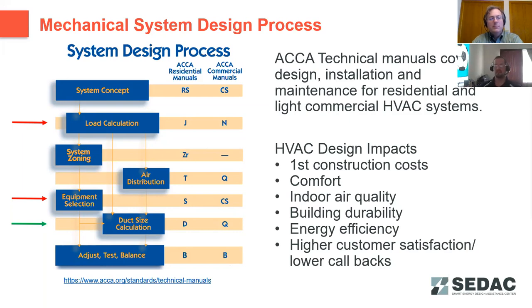for duct sizing. Although it's not a requirement of the code, it can be very beneficial because it helps ensure that the airflow through your duct system is going to be evenly distributed and meet the individual space loads within your structure. It's not uncommon for a lot of residential buildings to see balancing dampers put in the ductwork, and on callbacks from the customer, or during finalizing of the house when they're doing final touch-up painting and things like that, they'll adjust those dampers in order to balance the airflow. If they'd done a Manual D calculation, they wouldn't need those at all. The ductwork would be properly sized to evenly distribute airflow throughout the house. So we do like to highlight that Manual D is an option and can potentially reduce callbacks and issues with uneven heating and cooling within structures.